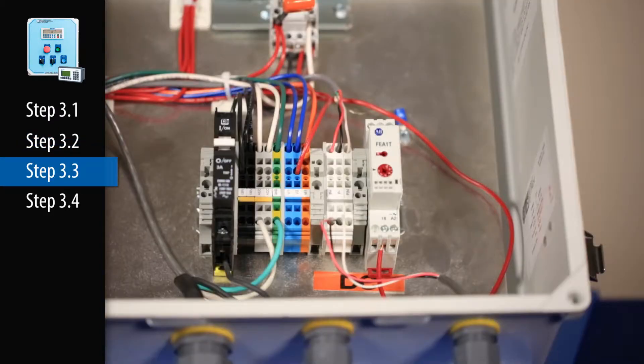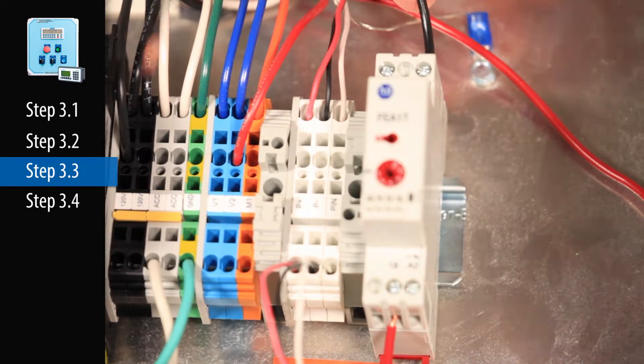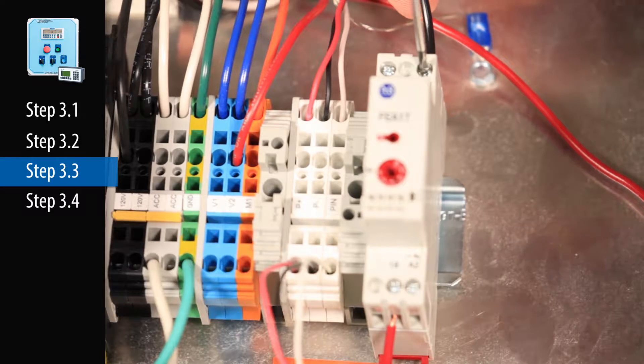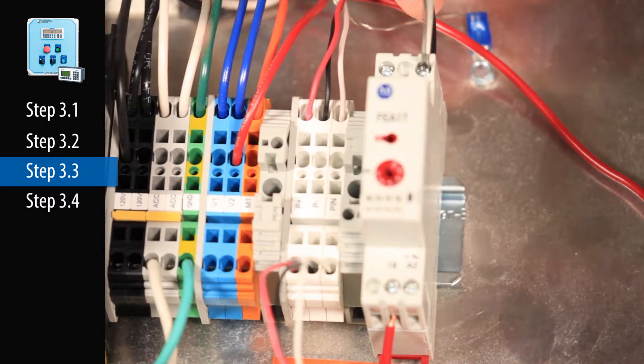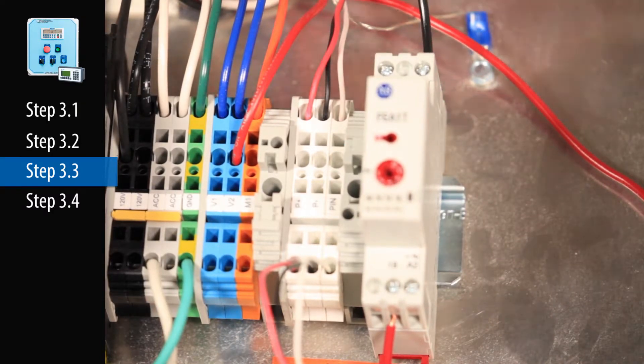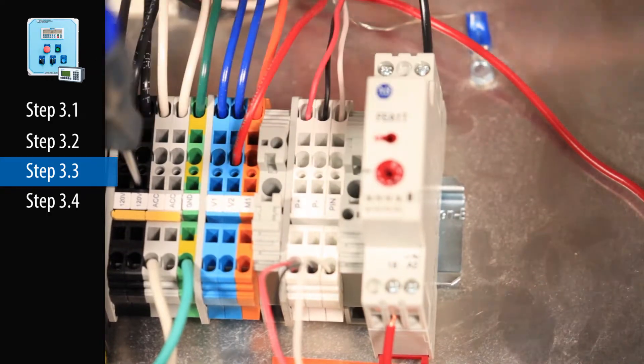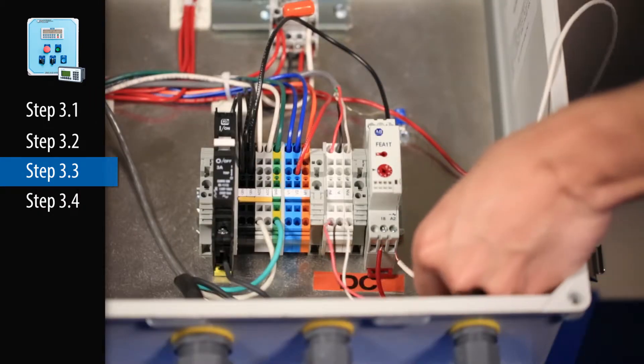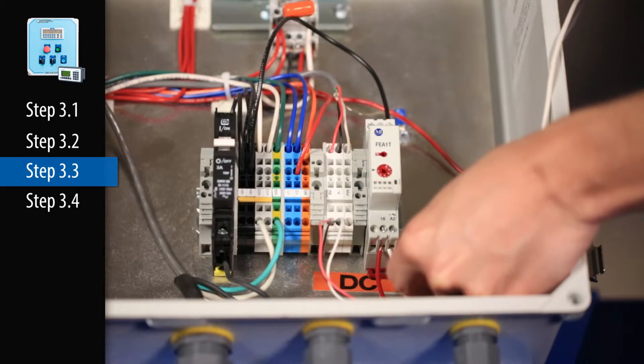Step 3.3. Connect 120 AC power to terminal A1 on the relay timer. If available, you can use the auxiliary terminal blocks on or near the incoming power. However, do not jump from the incoming power supplying the circuit breaker. Connect AC common, or neutral, to terminal A2 on the timer.